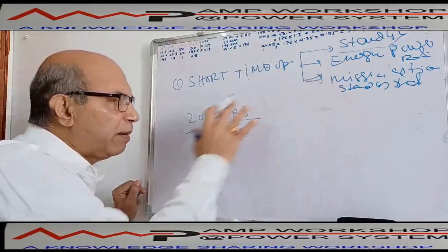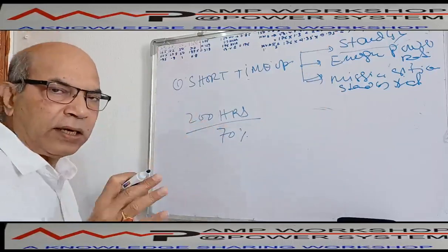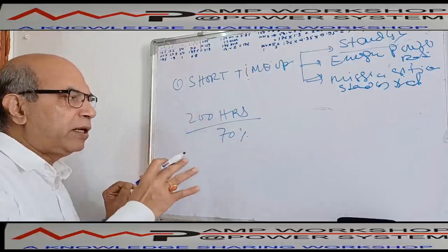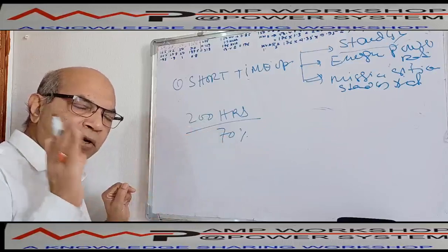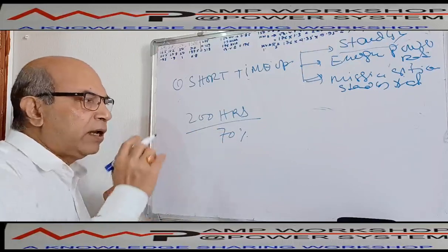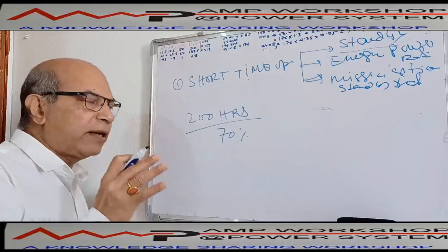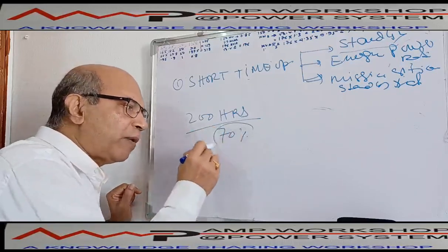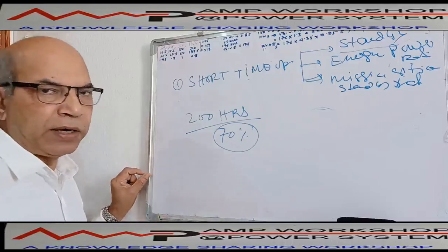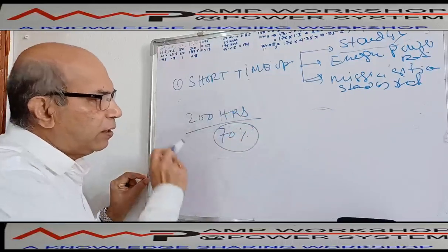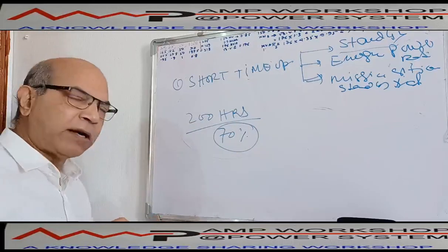In the case of the emergency power supply rating, our EPS rating, it is done the same way. In that case also, the machine shall not run more than 200 hours in a year, and it is not recommended to run the machine on the nameplate rating. It should always be less than the nameplate rating, but the average load factor will not be more than 70% of the nameplate rating. So if that is the operation requirement, then we go for the emergency power standby rating.